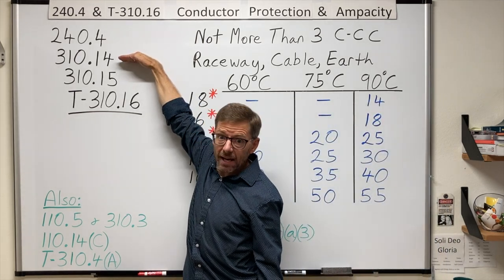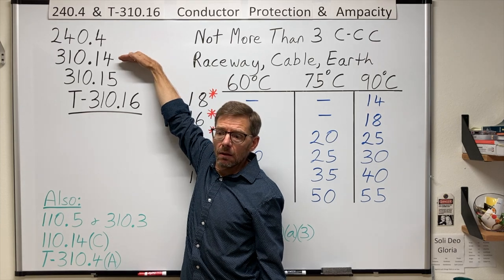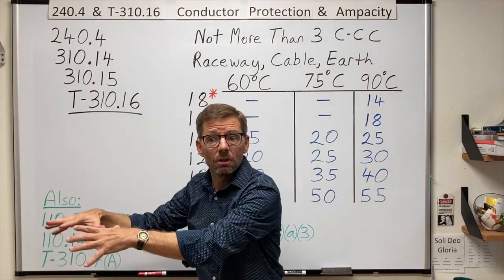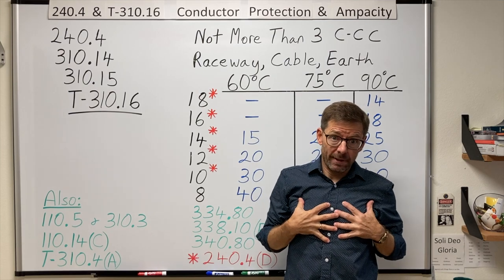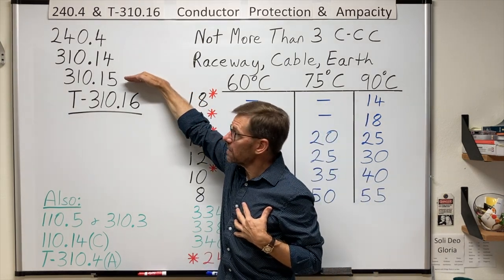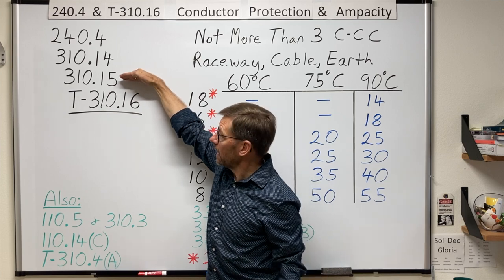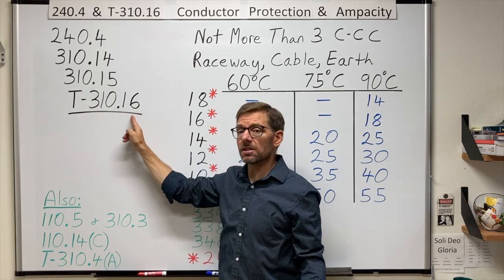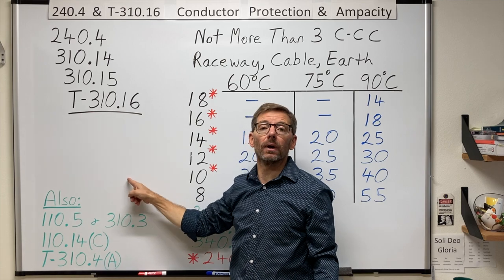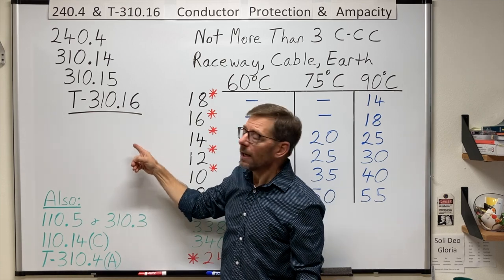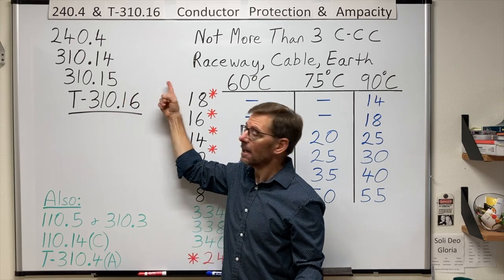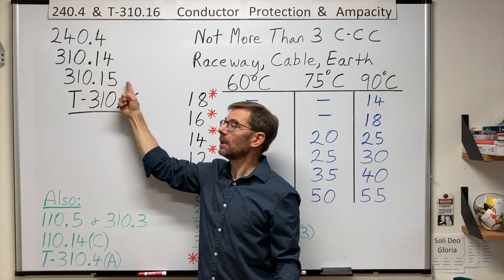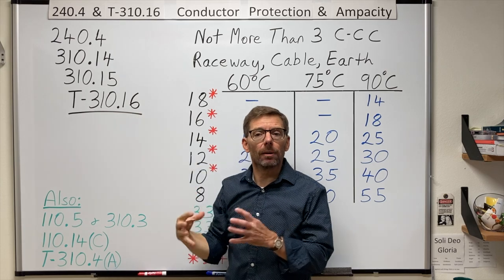But generally speaking, we're using the ampacities in 310.14. And it gives me two options in there. I can do a bunch of calculations under engineering supervision. Or, more from an electrician's perspective, it says, look at 310.15. And in there, I'm given any number of tables to use, a half dozen of them. Table 310.16 down through .21. So again, I have to finish the sentence. It says, use these tables as modified in 310.15, a through f. And we will talk about some of those in a couple moments.